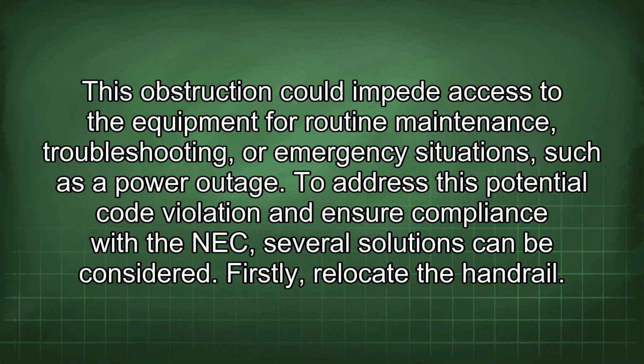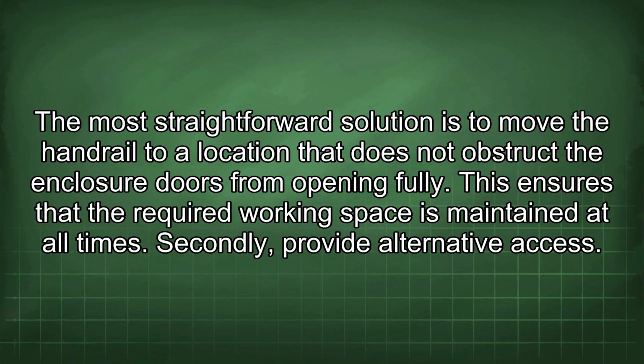To address this potential code violation and ensure compliance with the NEC, several solutions can be considered. Firstly, relocate the handrail. The most straightforward solution is to move the handrail to a location that does not obstruct the enclosure doors from opening fully. This ensures that the required working space is maintained at all times.